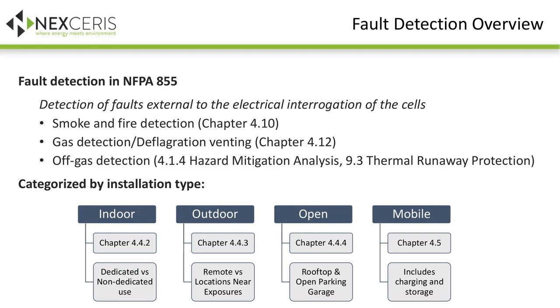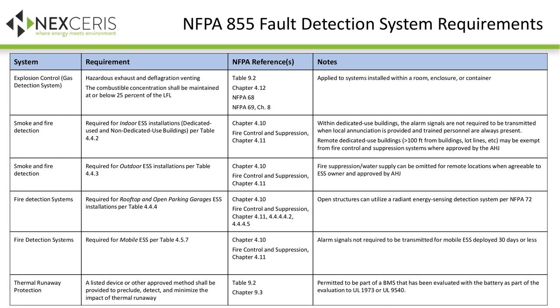This next slide is a little like eating dry toast, so I won't go over it much—it's here mainly for reference. It shows some specific references and exceptions in the current version of the standard for things like smoke and fire detection as they pertain to indoor, outdoor, open installations, and mobile. In Chapter 4.12, there's a requirement for certain systems, as noted in the notes column, for deflagration venting to get rid of the hazardous exhaust that comes out of the cells under failure conditions. The idea is to use a gas detection system to keep the overall environment below 25% of the lower flammability limit, again for the purpose of preventing deflagration.